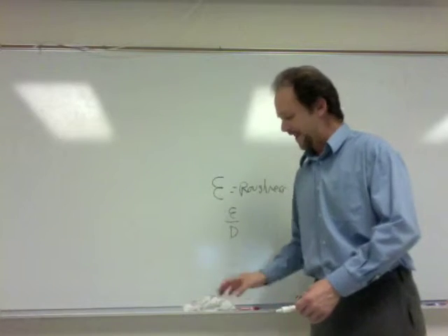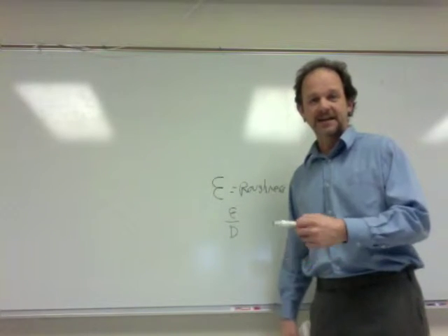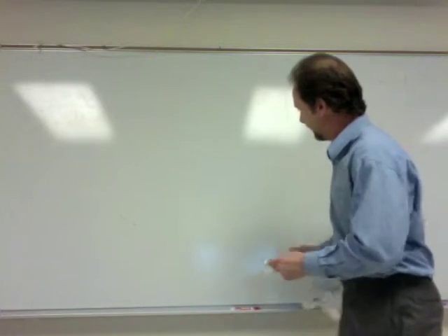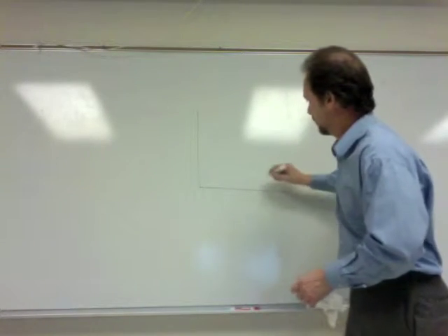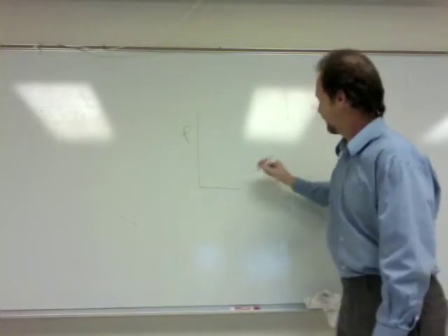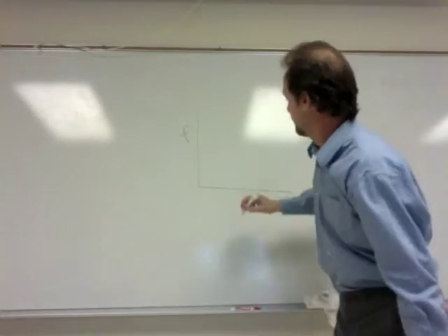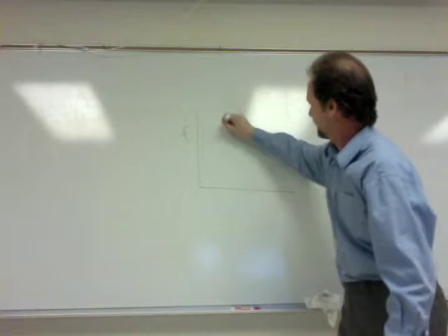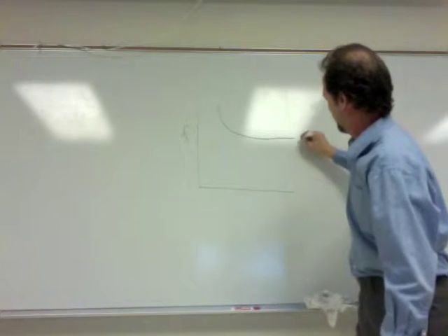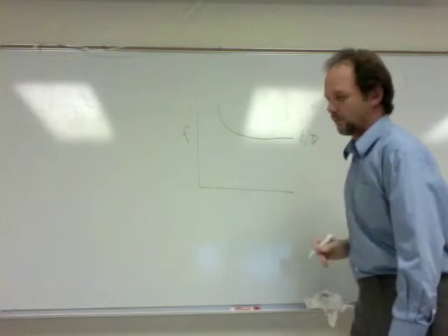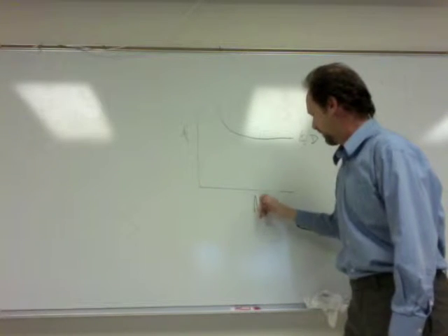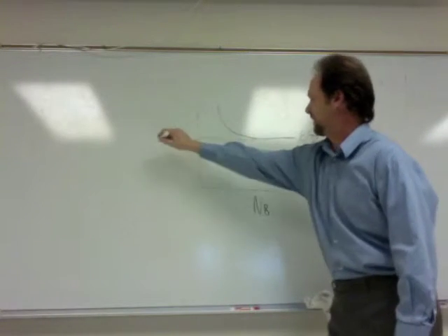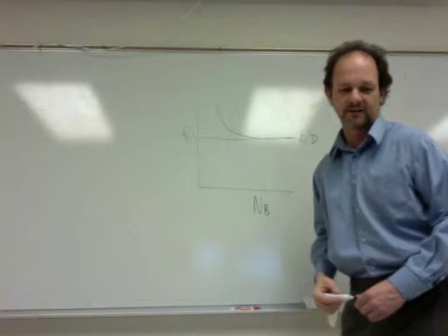That will get you to a good guess on the Moody diagram, because you remember the Moody diagram will look something like this, where this is the friction factor F. You've got something that's for a long time very stable here, because this is a particular curve, which is relative roughness, and here is your Reynolds number. If you know your relative roughness, you can quickly guess at your friction factor. So that's the start of that.